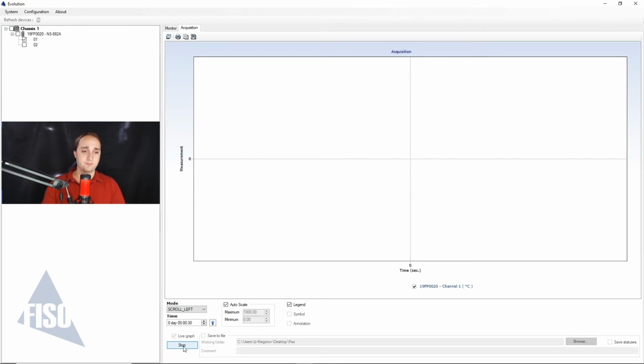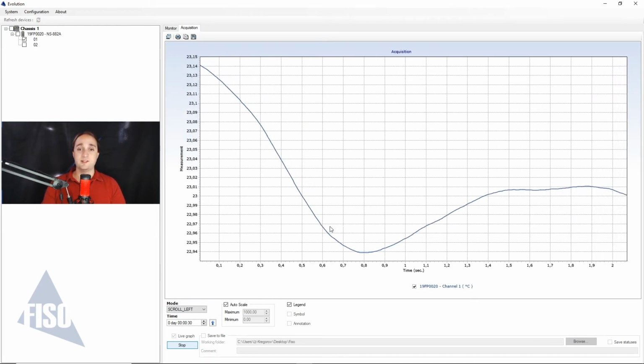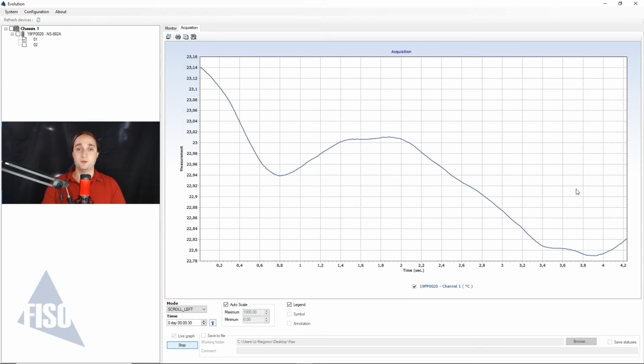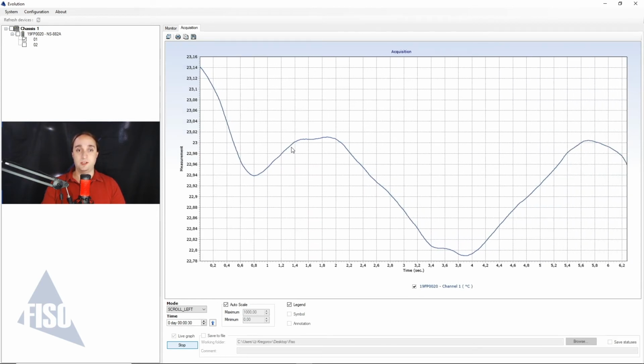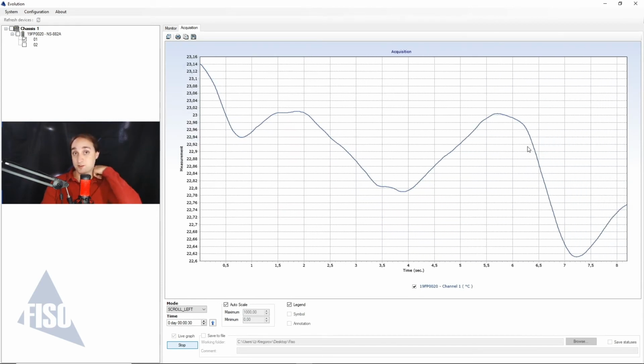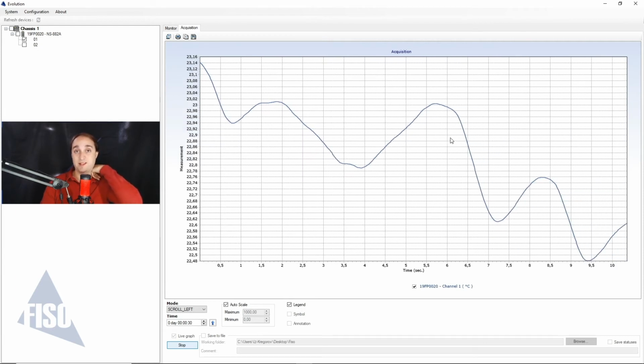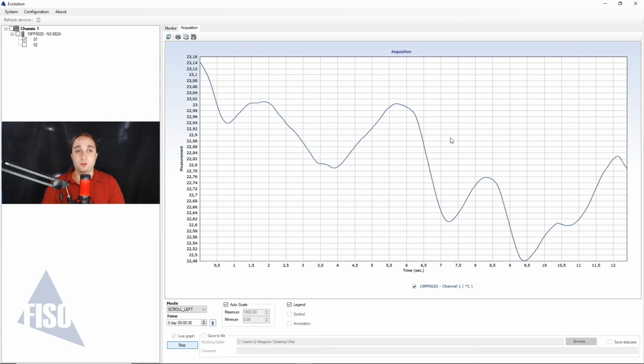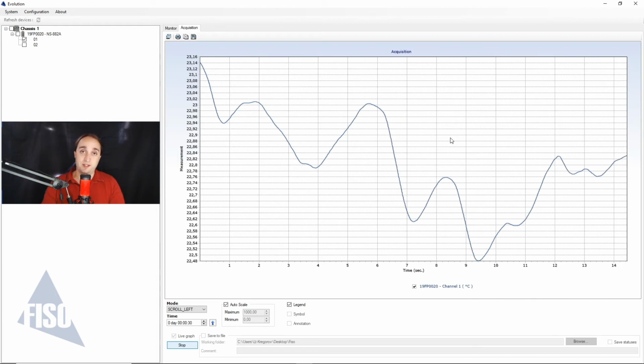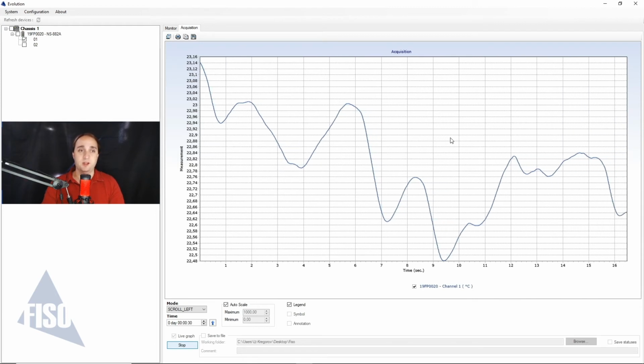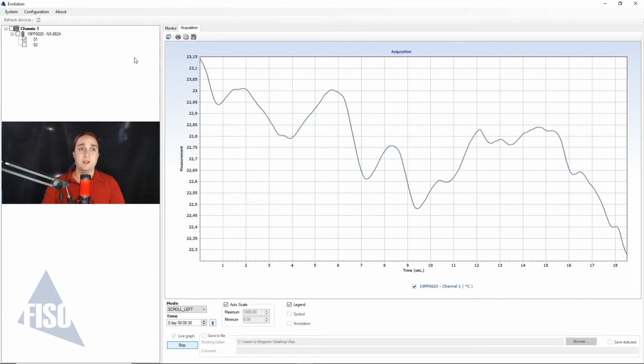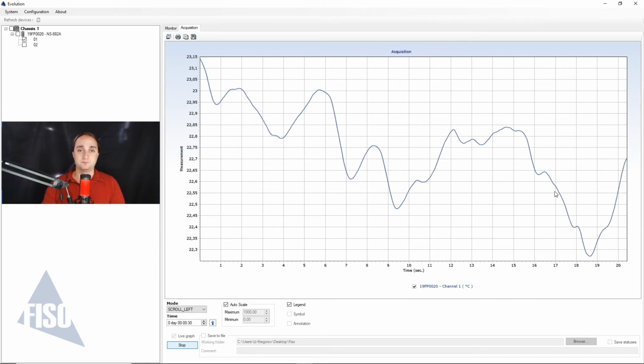So we're going to hit start. And as you can see right now, the software is monitoring and taking note of the real-time measurement of the sensor for each second that passed. Now, the SPC-HR module is able to take 250 measurements per second. So that's a lot of little points, so we get a very good mean value.